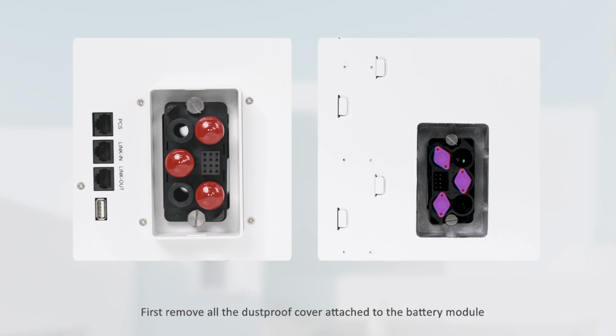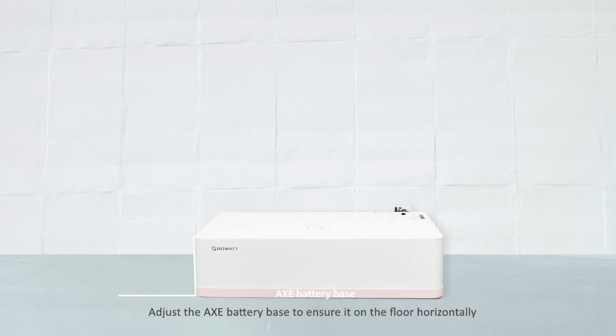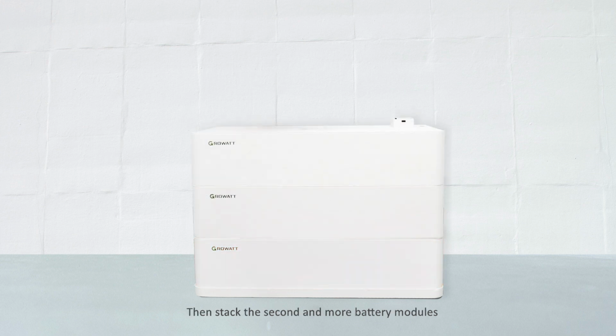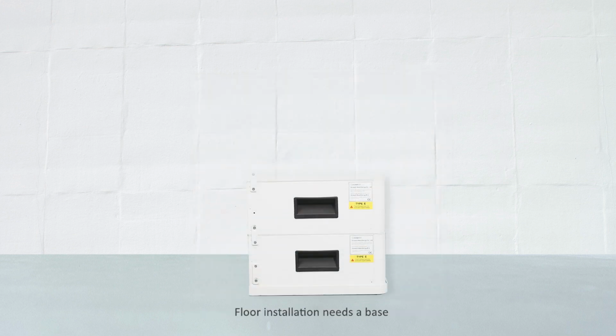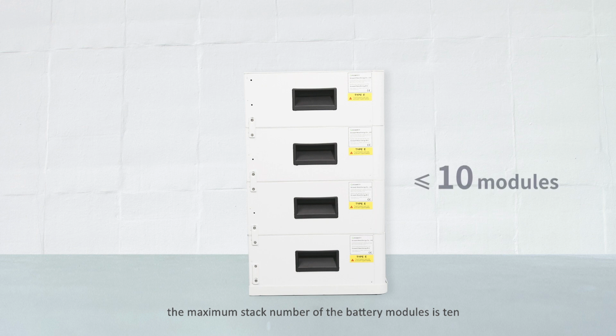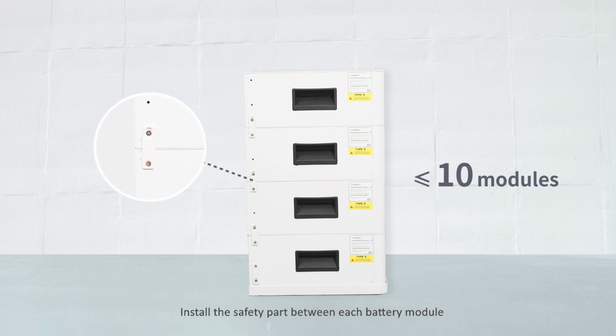First, remove all the dust-proof covers attached to the battery module. Adjust the AXE battery base to ensure it is horizontal on the floor. Stack one AXE battery module on the base. Then stack the second and more battery modules. Floor installation needs a base. The maximum stack number of the battery modules is 10. Install the safety part between each battery module.